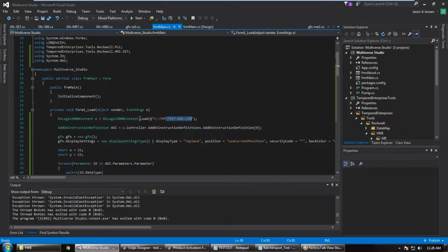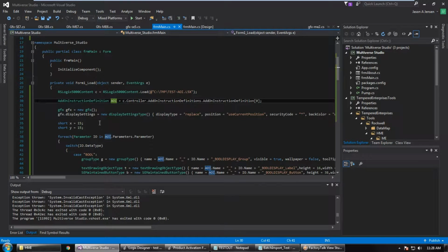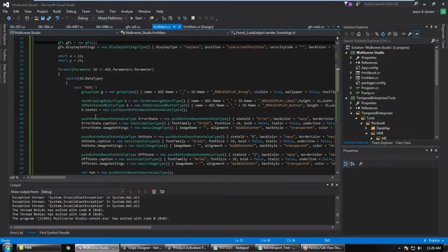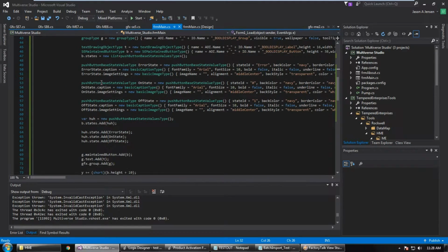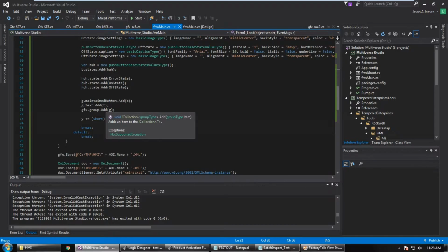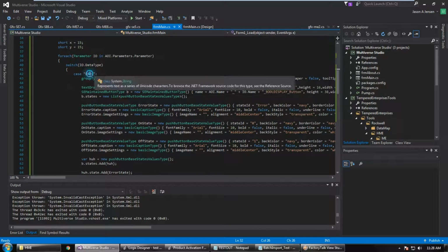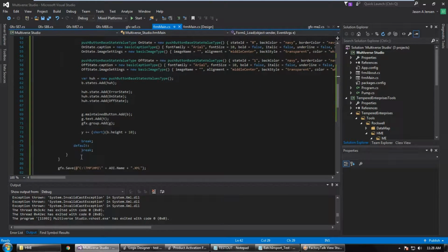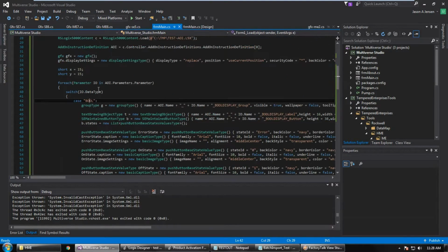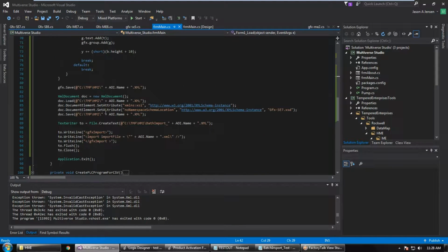So this new demo, I already have an add-on instruction definition export file, and I am loading that file up, accessing the first add-on instruction in it, and I am generating push buttons for every single input parameter that is of type bool. I could overload it for real or really any data type, and then I could do a recursive loop so that I could handle UDTs and stuff like that. And then I output that screen to this folder.